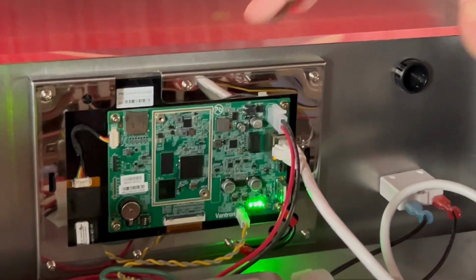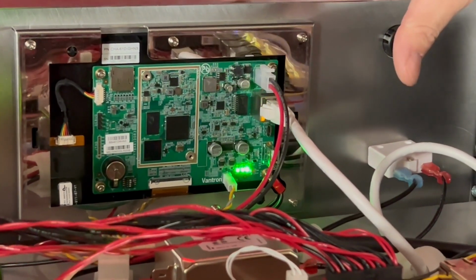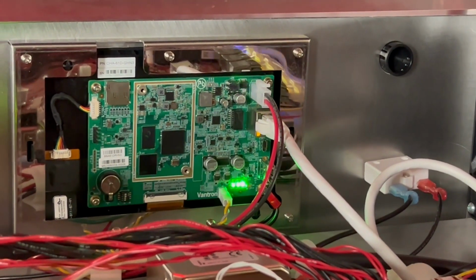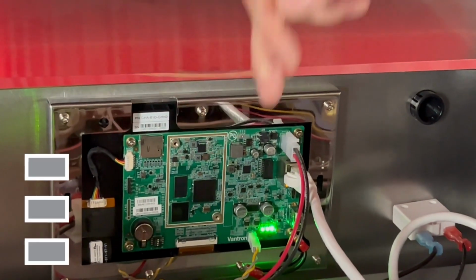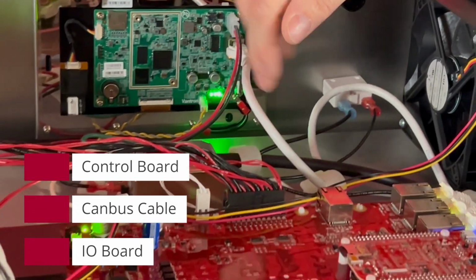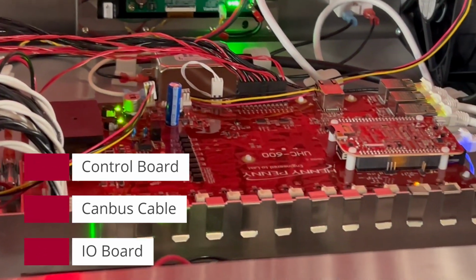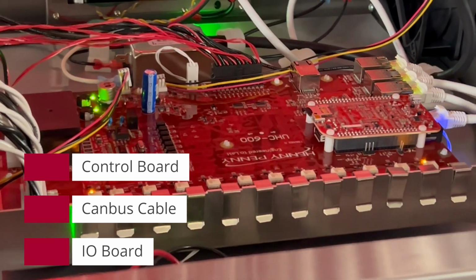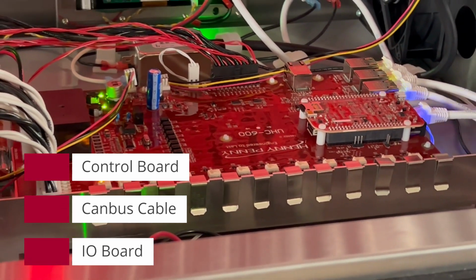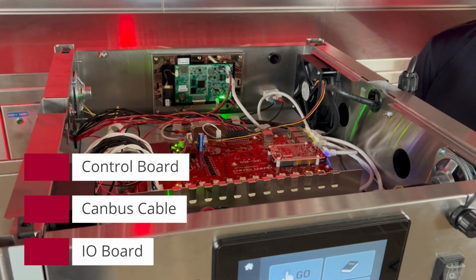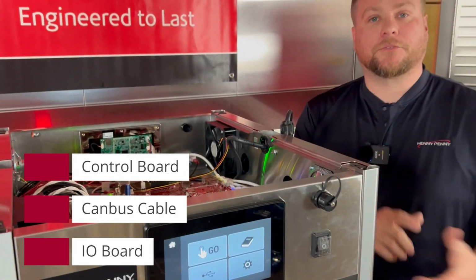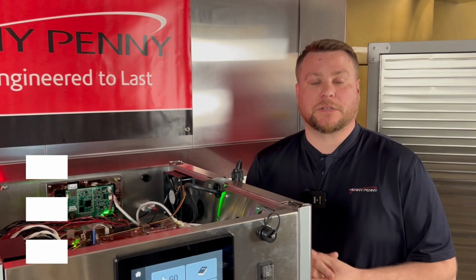So remember, the components involved that could be a failure point is going to be either 1, our control, 2, our CAN bus cable, or 3, our I/O board. So when it comes to taking parts with us to the job site, we want to take those 3 components involved to help try to have a first-time fix rate when it comes to this error code.